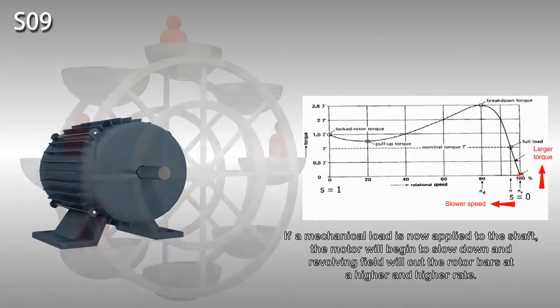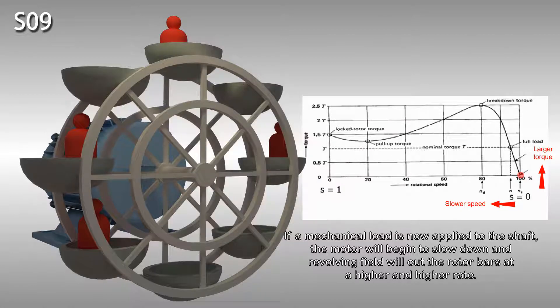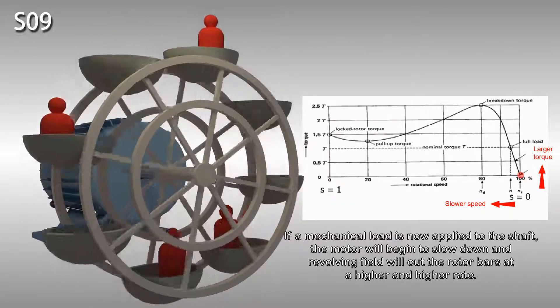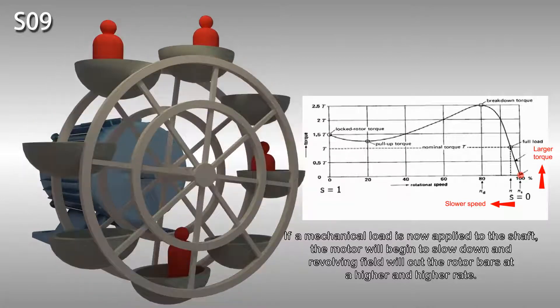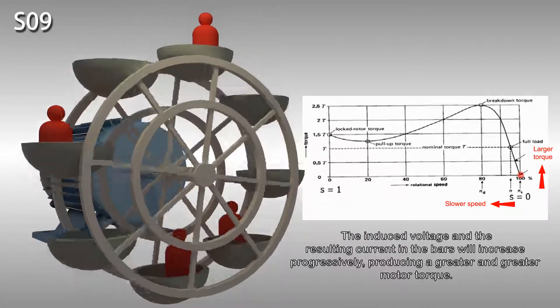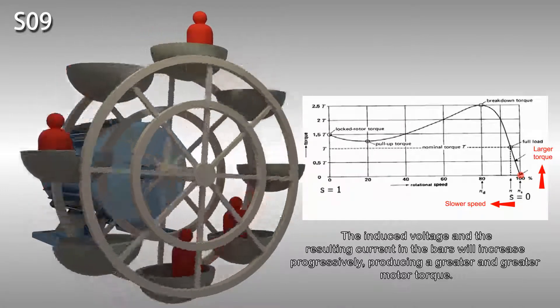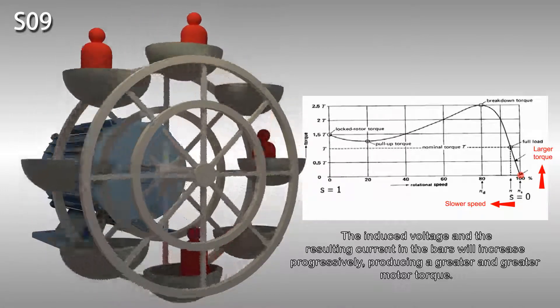If a mechanical load is now applied to the shaft, the motor will begin to slow down and the revolving field will cut the rotor bars at a higher and higher rate. The induced voltage and the resulting current in the rotor bars will increase progressively, producing a greater and greater motor torque.